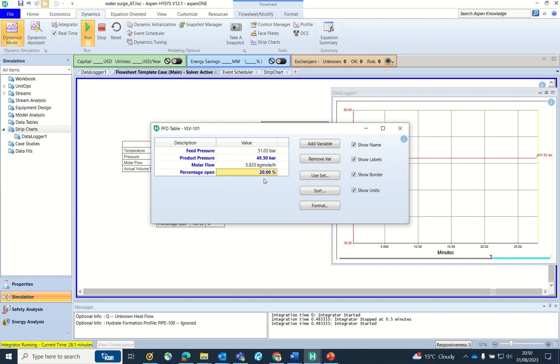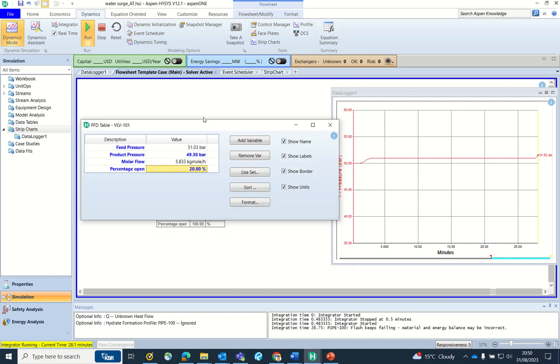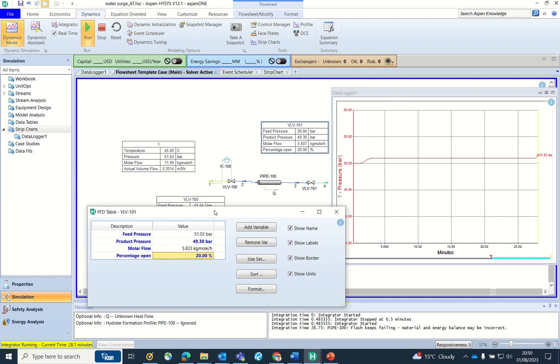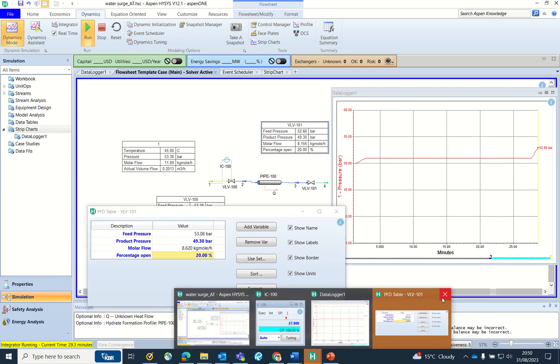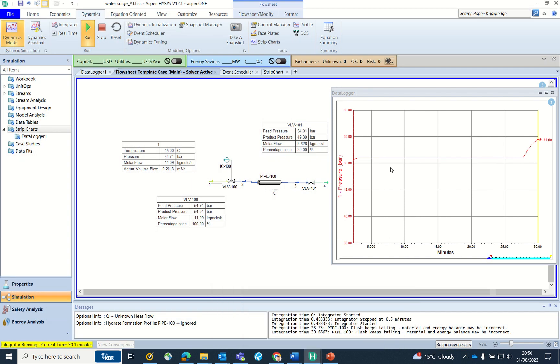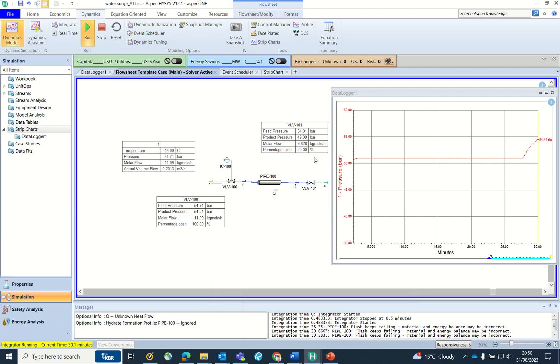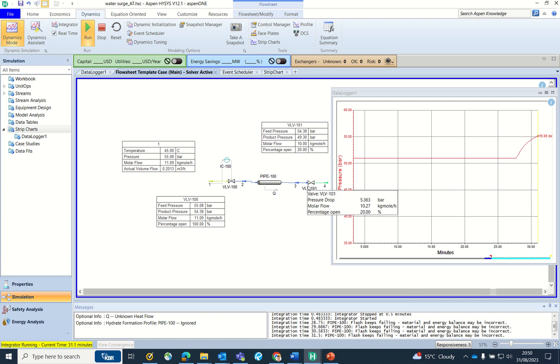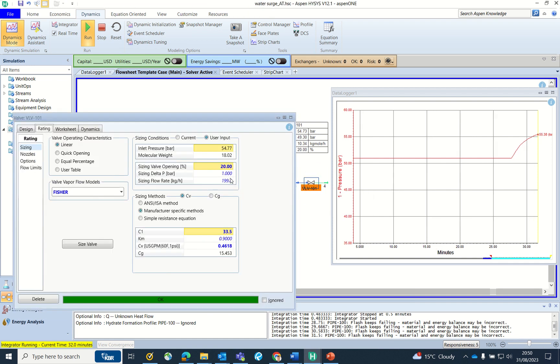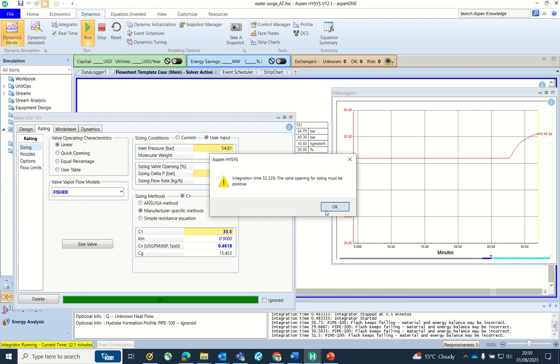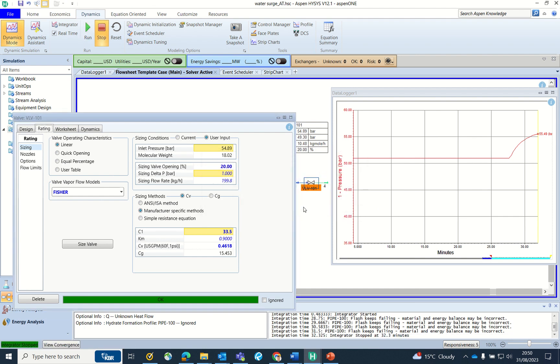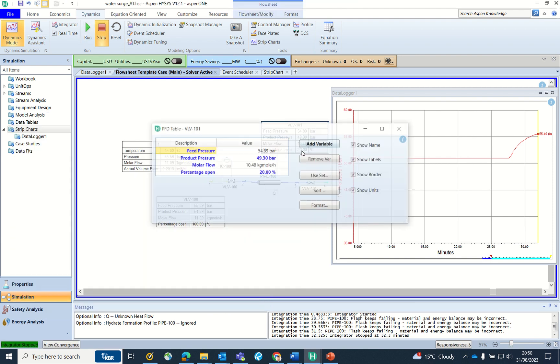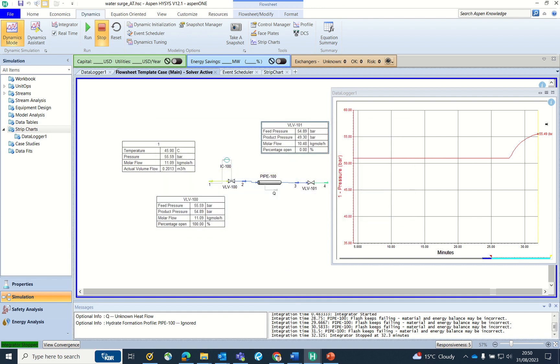You can see 20% I have done, but I think that is not the right way of doing that. So I have used this - if I go here 20% it gives you a sizing. I have changed here, you can see 20% valve opening and there is surge in the pressure.